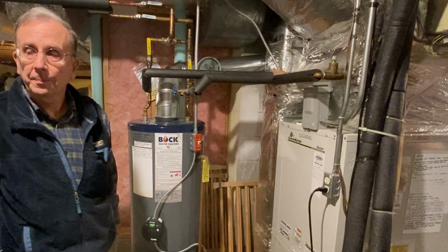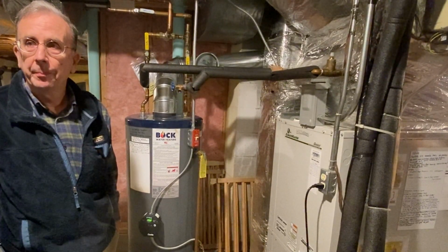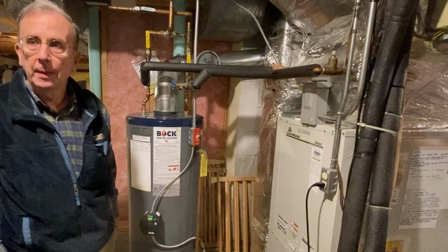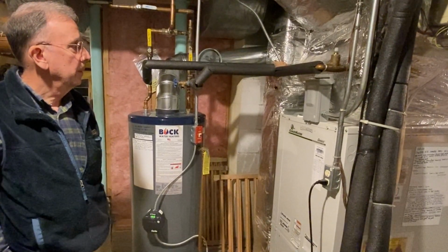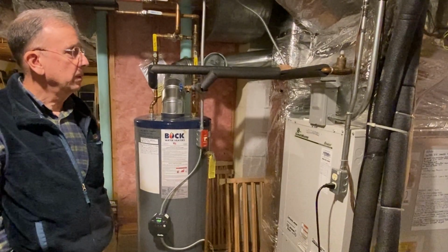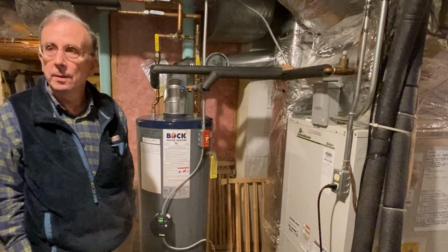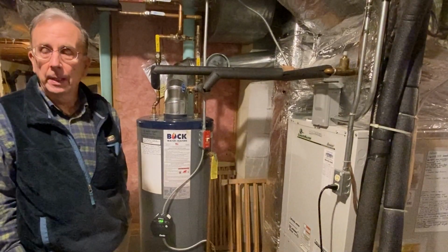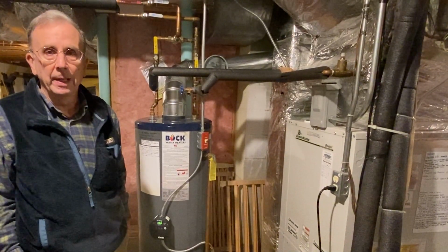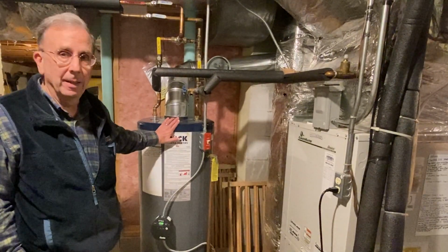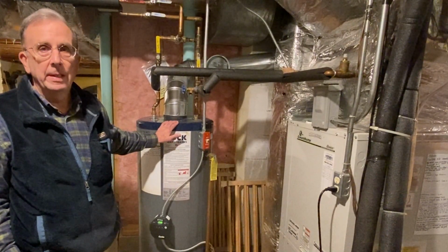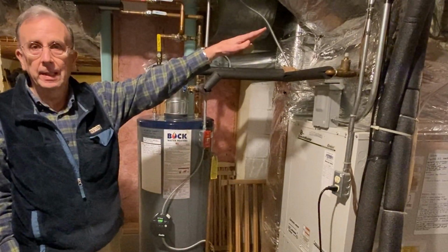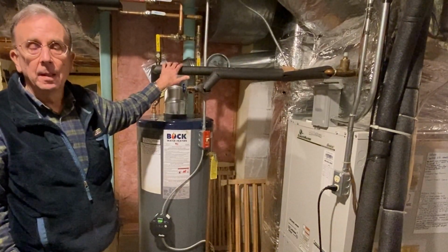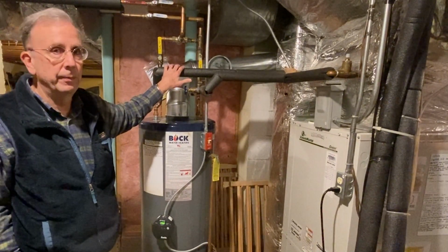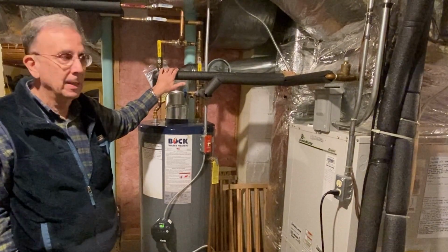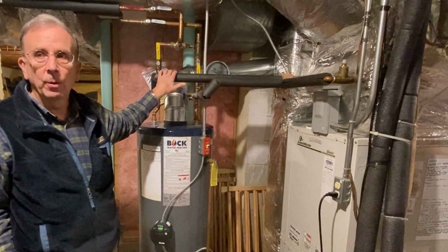I would just add one thing, that we only need a boost to the geothermal system from the oil hot water heater when it's extremely, extremely cold out, like below 0 Fahrenheit. I would say it depends on conditions. If it's calm outside, then the temperature has to go down around 0 for this backup heat to be needed. If it's 10, 15, 20 degrees with a 30-mile-an-hour wind outside, then the backup heat may kick in on those occasions too. But what we've observed is that the backup turns on for 2 or 3 minutes and then goes off.